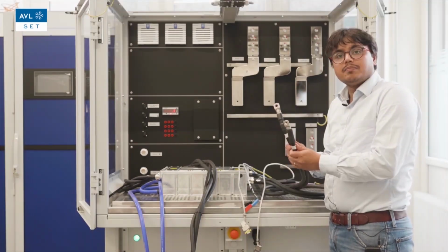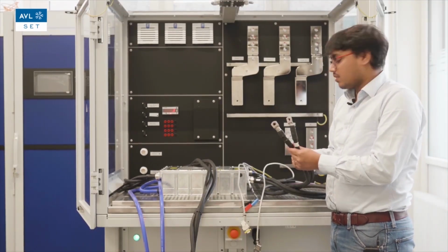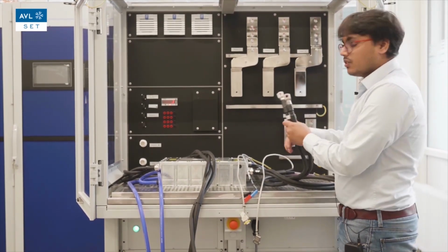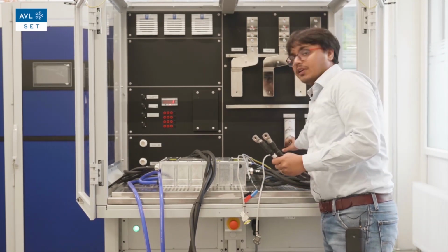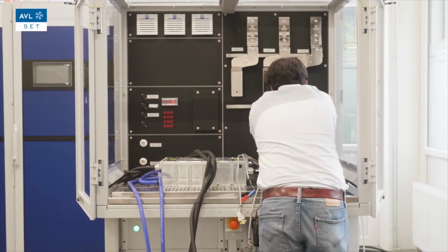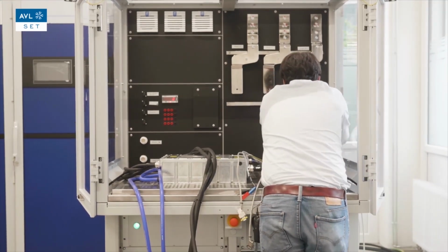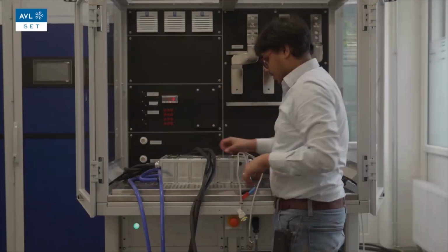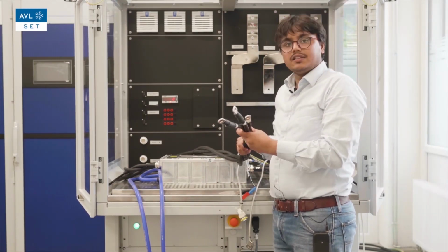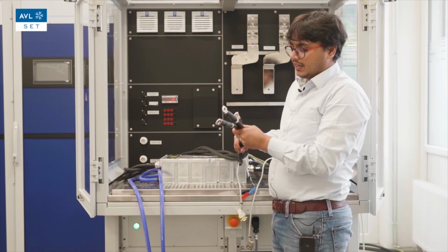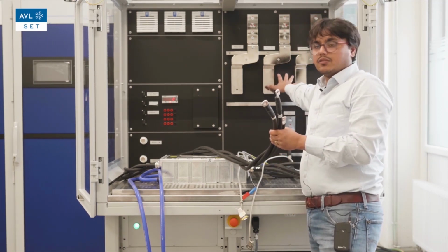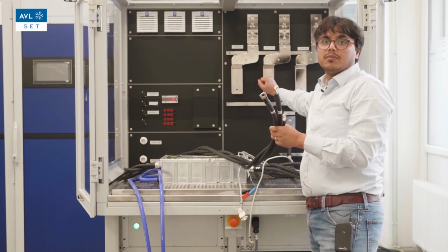These are the two DC plus and DC minus cables coming from the inverter. Now I will connect them to the high voltage DC power supply terminals on the inverter table here. Okay, so these are the three-phase AC cables, and I will connect them to the three-phase AC terminals of the emulator, which are terminated here on the inverter table.